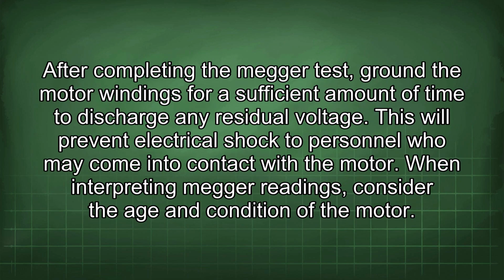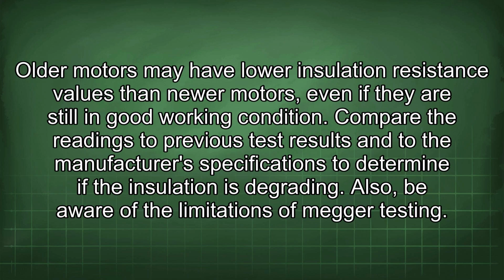After completing the Megger test, ground the motor windings for a sufficient amount of time to discharge any residual voltage. This will prevent electrical shock to personnel who may come into contact with the motor. When interpreting Megger readings, consider the age and condition of the motor. Older motors may have lower insulation resistance values than newer motors, even if they are still in good working condition. Compare the readings to previous test results and to the manufacturer's specifications to determine if the insulation is degrading.